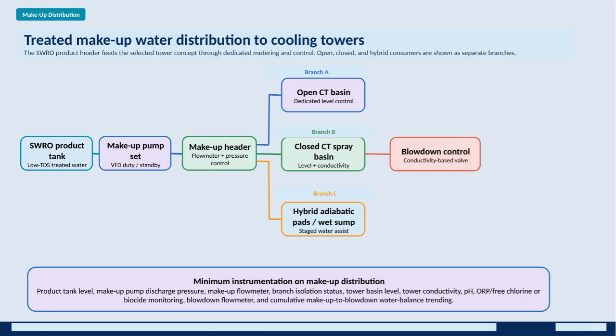The open cooling tower basin maintains water levels through dedicated controls, while closed cooling tower spray basin monitors both water level and conductivity to maintain optimal conditions. For the hybrid towers, which combine adiabatic pads with wet sump, staged water assistance is provided to optimize cooling efficiency. Additionally, blowdown control is managed by a conductivity-based valve to regulate water quality and prevent scaling. Instrumentation is kept minimal but effective, monitoring critical parameters such as product tank level, pump discharge pressure, flow rate, isolation status of branches, basin levels, conductivity, pH, ORP, or free chlorine/biocide levels, and blowdown flow rates. This setup ensures a balanced water system with real-time monitoring of makeup and blowdown water volumes.